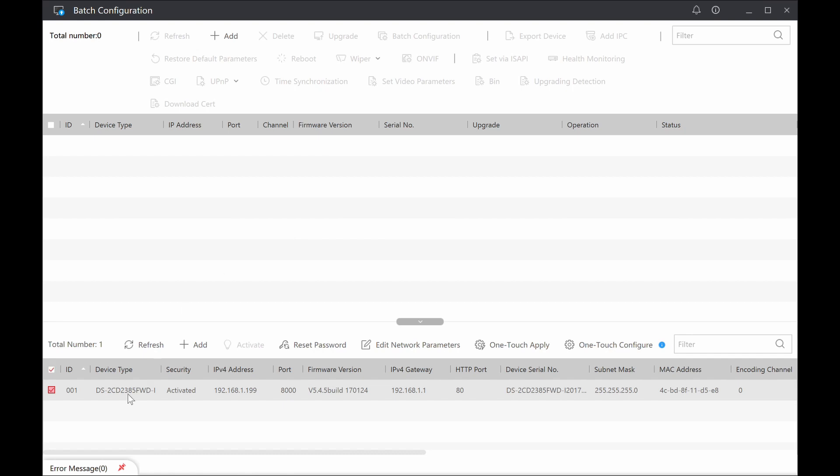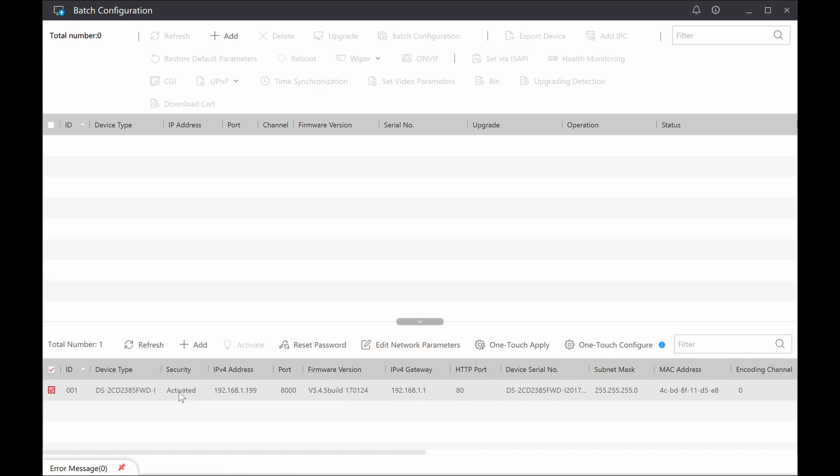So in this case, we've already activated this particular camera because I did this for a demo session in our training. So the camera is already activated, I've already given an IP address. But essentially what would happen is plug it into my network, power it up, run the software, and then from here it will come up with a device that's unactivated. And when you go to activate that, it will ask you for a username and password, an IP address if you wish to, and then go from there.